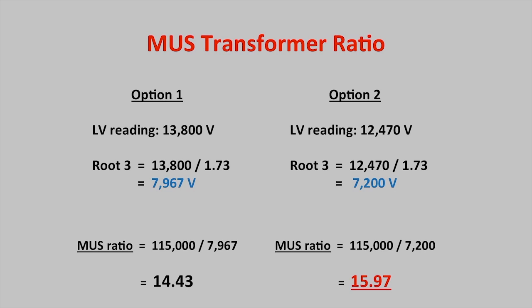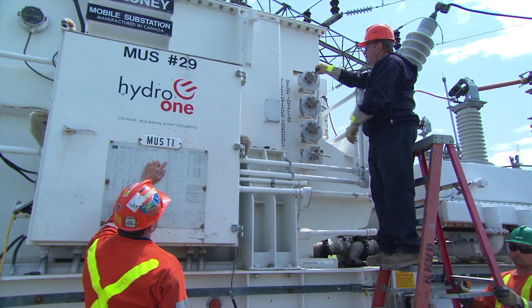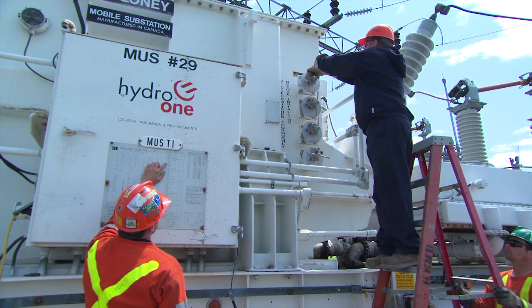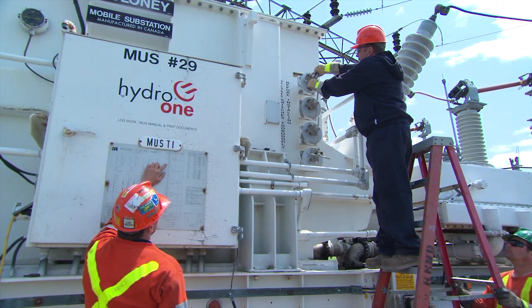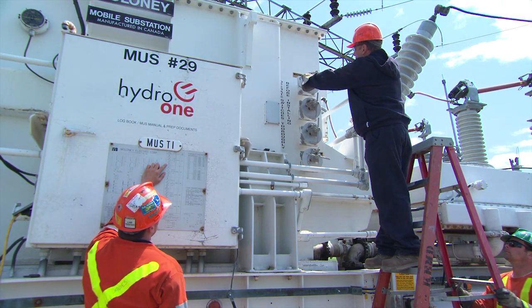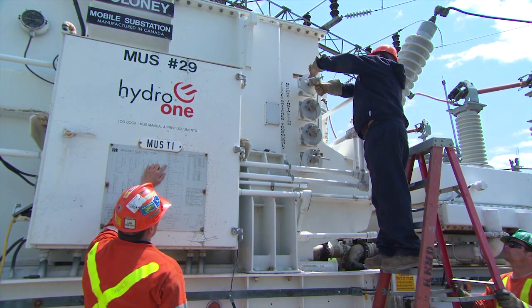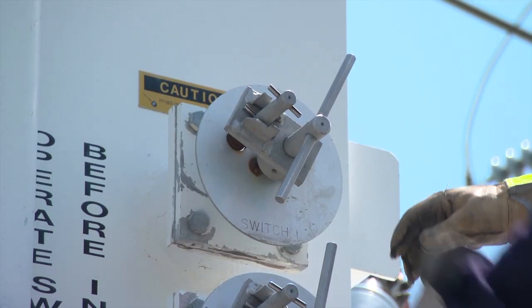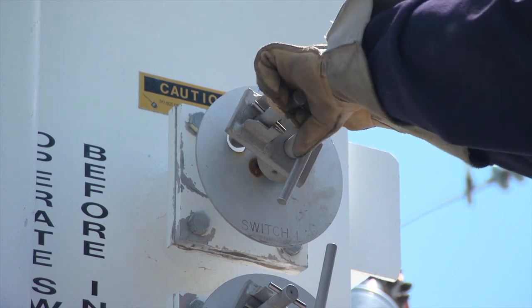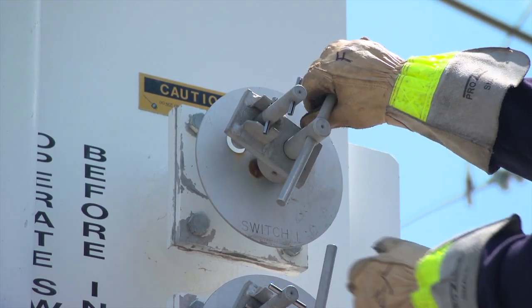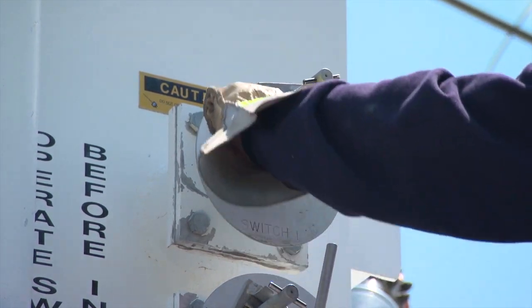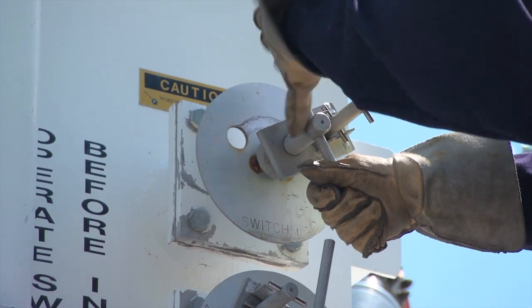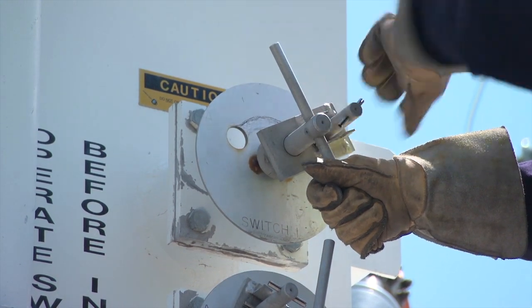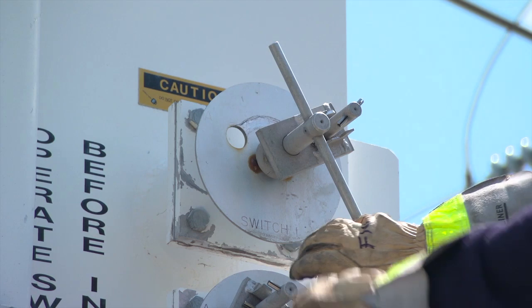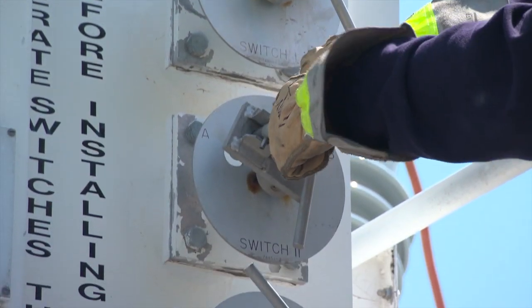Refer to the MUS nameplate data to determine what position the 4 MUS offload taps need to be set to for 12,470 volts. For this specific unit, the OCTC is operated by releasing the centering pin, rotating the handle, and repositioning the centering pin into the locked position. The final ULTC tap position will be selected to match the operating conditions when paralleling the MUS and DS.